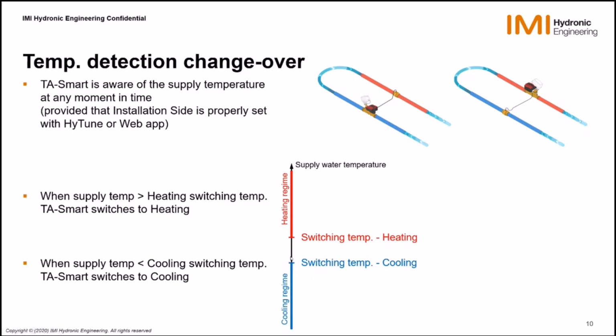Well, actually nothing will happen. It will stay in cooling. And it's only when this temperature starts to increase that then the valve will consider, the water is definitely warmer. I am now in heating. So I know what a few amongst you might be thinking about. You say, yeah, but when the valve is shut, if I am changing the system, the valve will not know that I am now in heating until it is open.